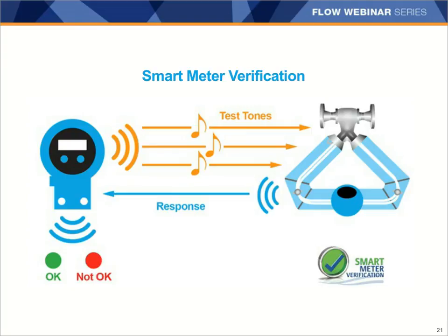intervals. And I'd like to talk here just about an example of an advanced diagnostic that can do this, and that's the smart meter verification diagnostic that Emerson uses to quickly check the health of a Coriolis meter from Micro Motion. Each meter is actually individually fingerprinted in the factory using multiple test tones. So we send frequencies to the meter, and we listen for the response. So one is at the natural frequency of the system, and then we send 2 at higher frequencies and 2 actually at lower frequencies. The response to each of these 5 frequencies is used to characterize the meter.